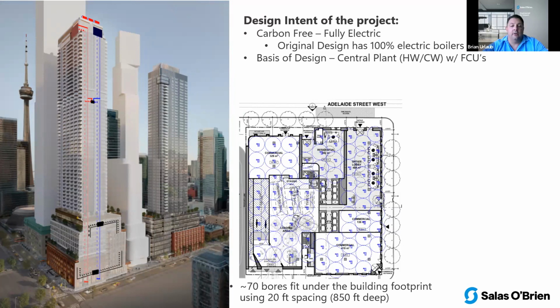The first thing we looked at was, okay, what's the footprint? You can see there, not very big for this size of a building. Maximum number of bores we could get, depending on spacing, was 70 to 80 bores. Typically in this market right now, the depth for most ground loops we're drilling to 850 feet. We started to look at even maybe going to 1,000 feet.